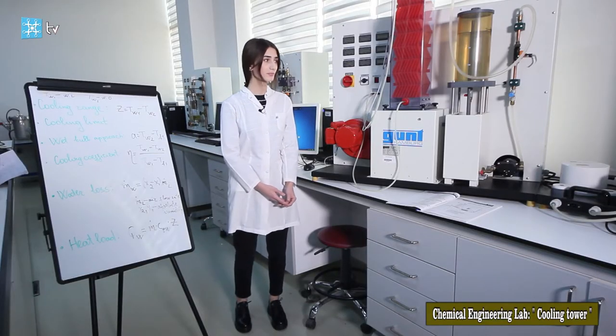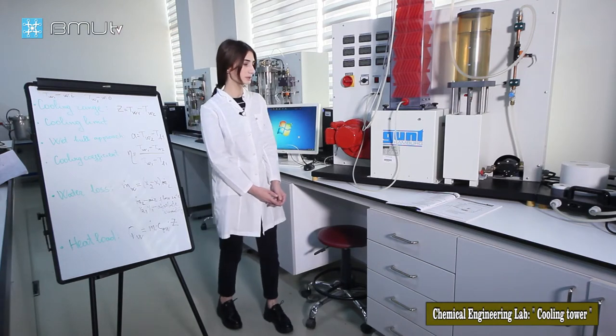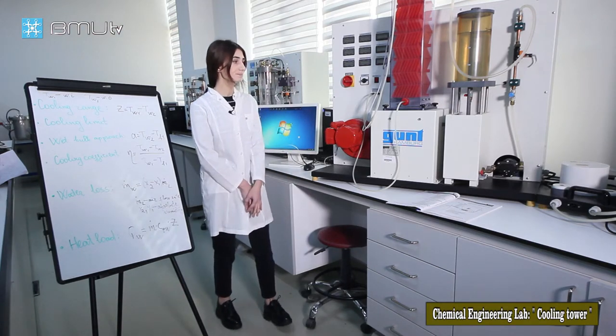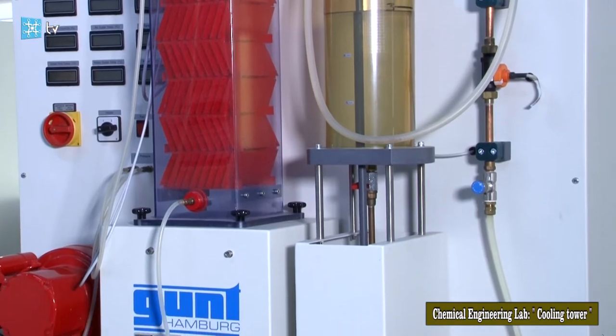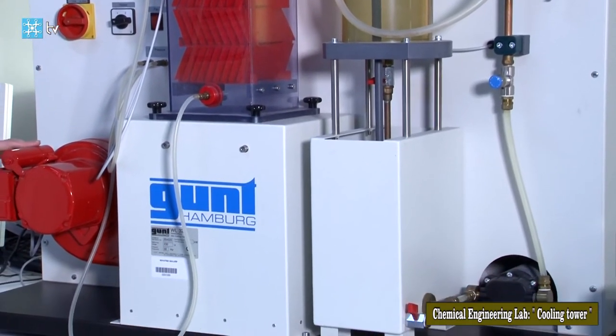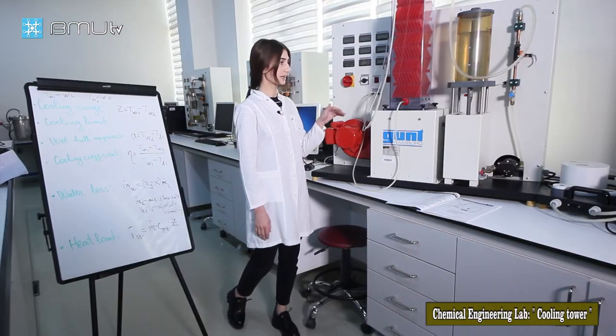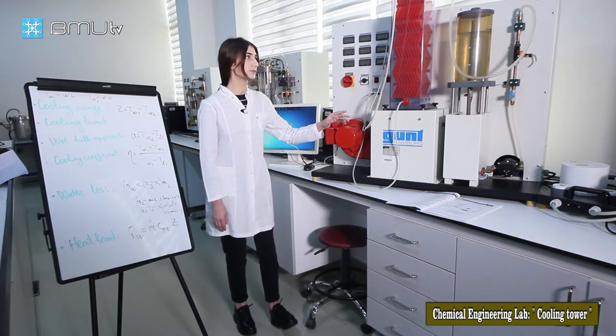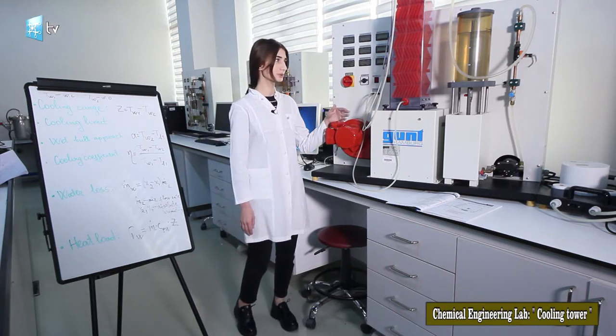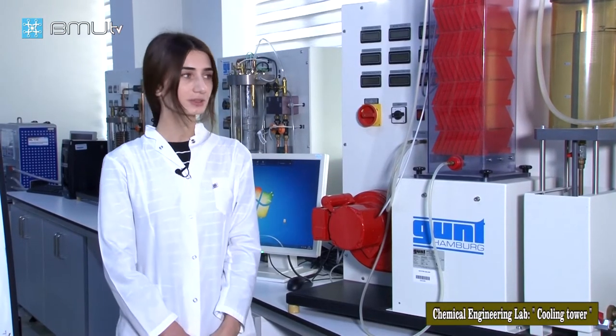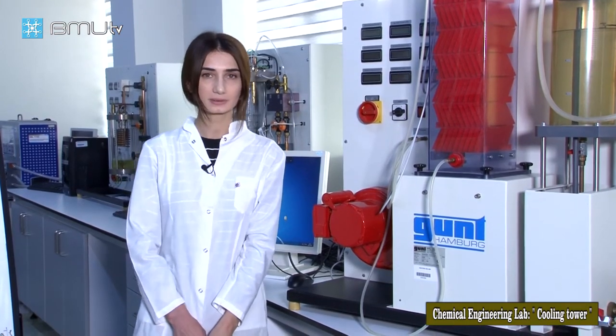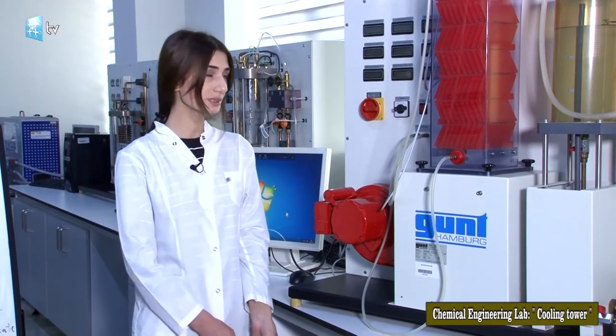This is the wet cooling tower with open circuit, and we use forced air ventilation in this case. Air and water come into direct contact, and water gives its heat to the air through convection. This is pure heat transfer without any material change, but there is also evaporation. Through evaporation, the water loses some evaporation heat, and so this further cools down the water.